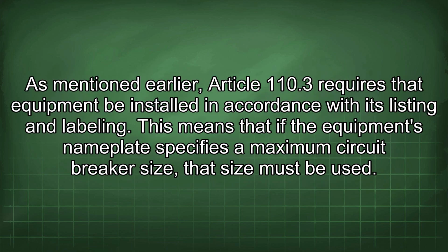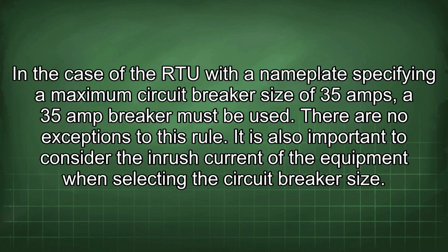As mentioned earlier, Article 110.3 requires that equipment be installed in accordance with its listing and labeling. This means that if the equipment's nameplate specifies a maximum circuit breaker size, that size must be used. In the case of the RTU with the nameplate specifying a maximum circuit breaker size of 35 amps, a 35 amp breaker must be used. There are no exceptions to this rule.